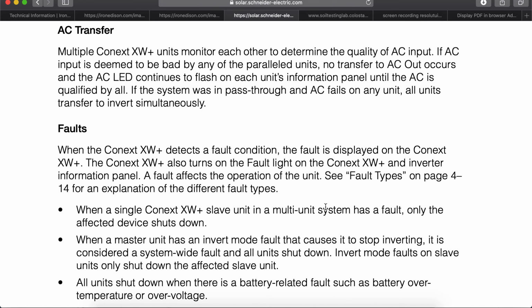AC transfer. When multiple Conext XW Plus inverter units are installed, they monitor each other to determine the quality of AC input. If AC input is deemed to be bad by any of the parallel units, no transfer to AC out occurs, and the AC LED continues to flash on each unit's information panel until the AC is qualified by all. If the system was in pass-through and the AC fails on any unit, all units transfer to invert simultaneously.